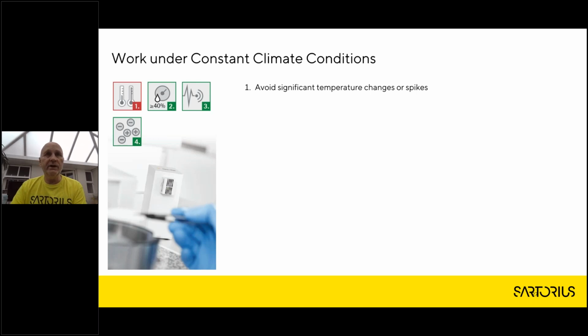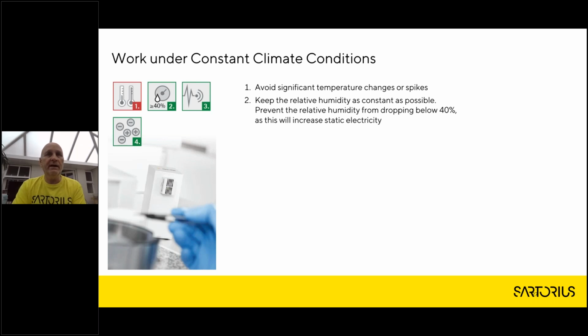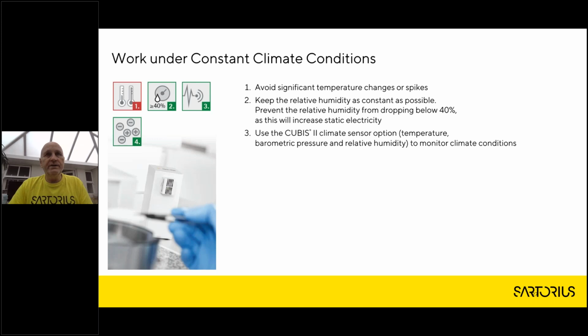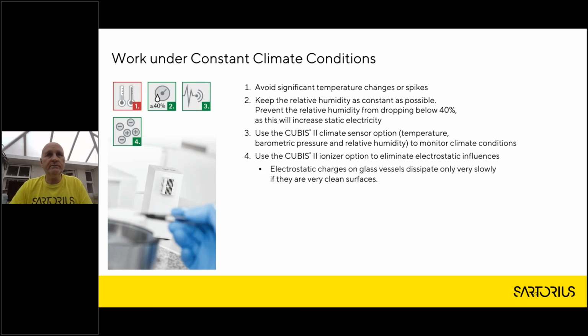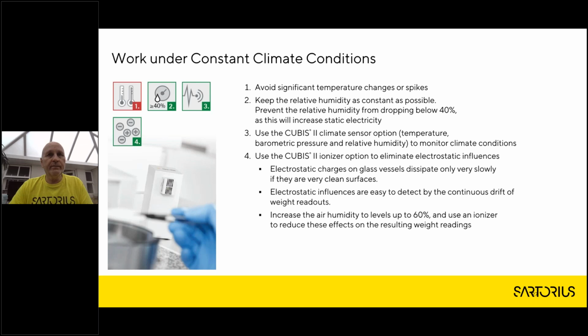So if we can, we should control the temperature within the laboratory and the relative humidity, keeping it constant and preferably not dropping below 40%, as we talked about before, because that increases the effect of any static electrical charge. We do have on Cubis 2 a climate sensor option, which clicks into the back of the draft shield, which measures temperature, barometric pressure, and relative humidity to monitor the climate conditions. We also have the option of the inbuilt Cubis 2 ionizer, the 4-point ionizer, to completely eliminate any static charges on your sample or your tare vessel. And we talked about increasing the humidity within the laboratory, if you can, to 50 or 60% to reduce the effects of static charge.